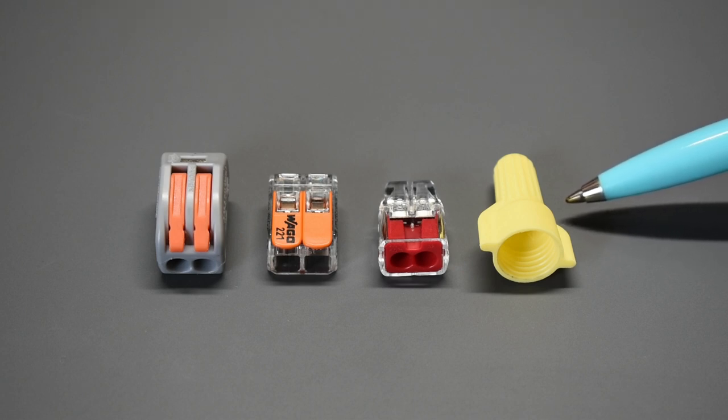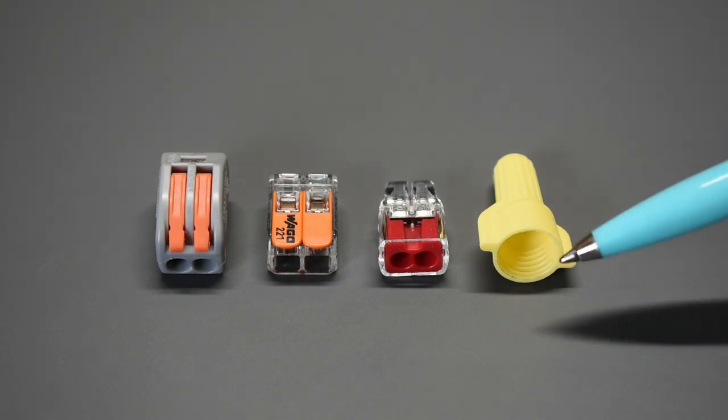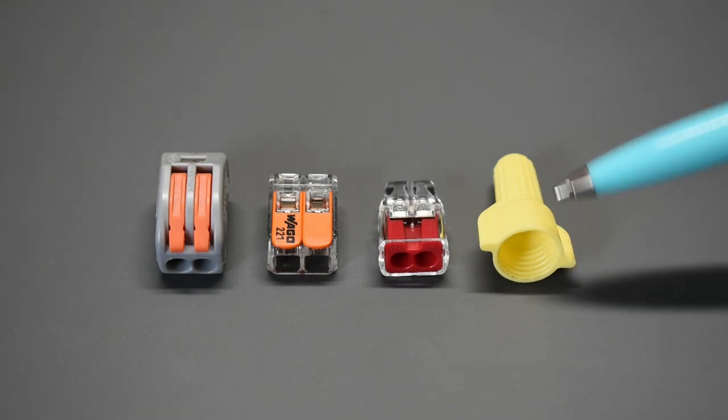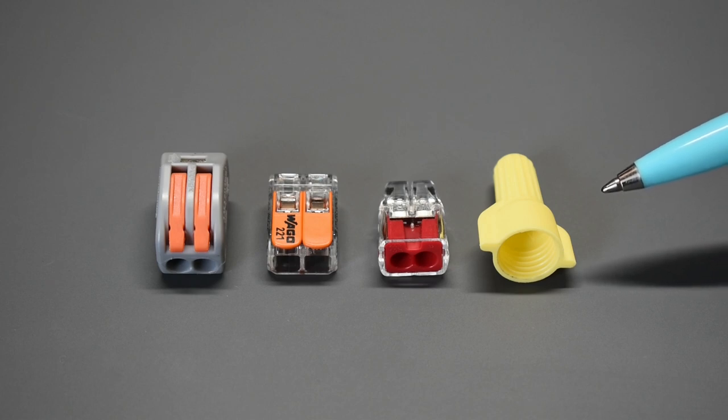While it's under test, we're going to measure voltage drop across the connector. And after 15 minutes, we're going to measure the temperature of each connector using my thermal imaging camera.